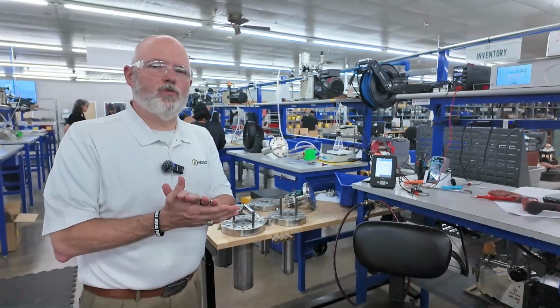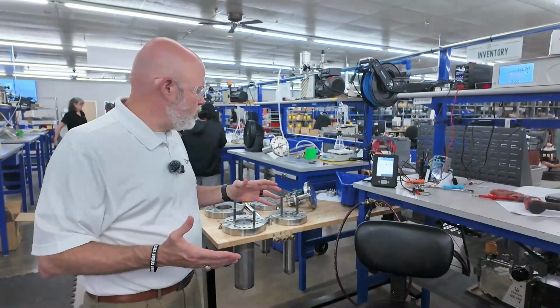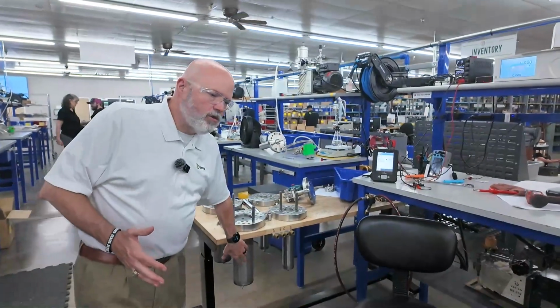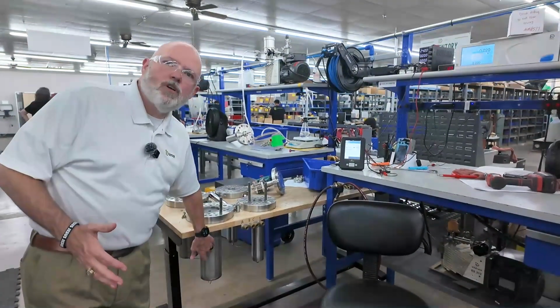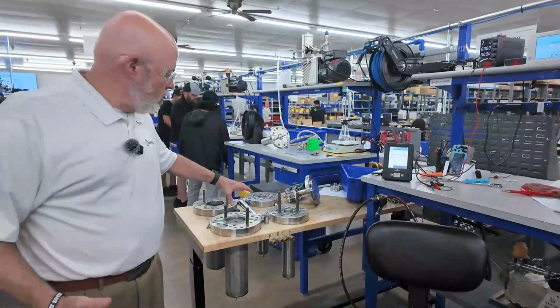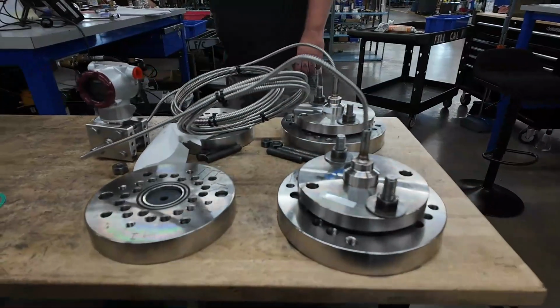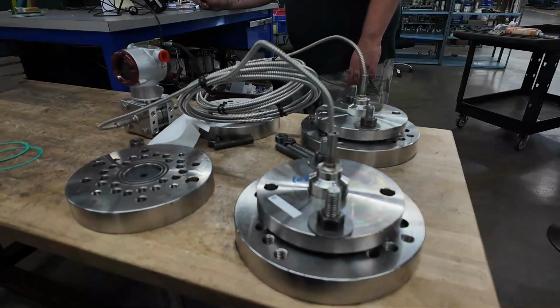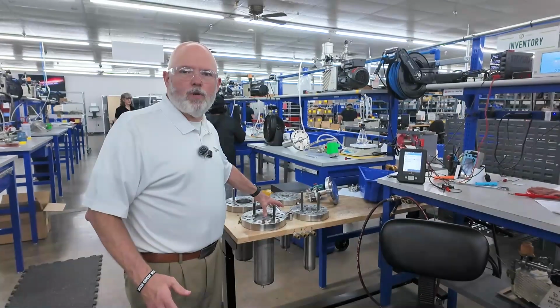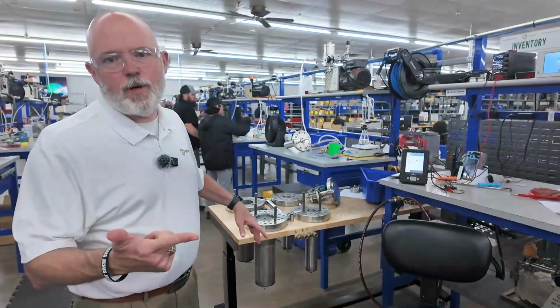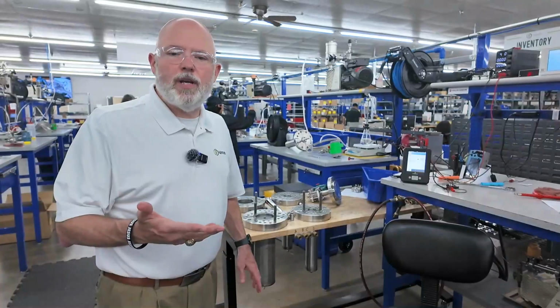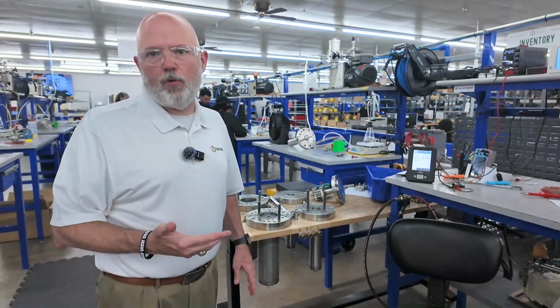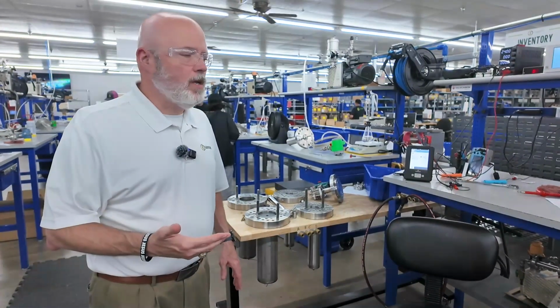So what we will do is calibrate these units. We simulate the process pressure right here through these fixtures. We mount the diaphragm seals up and simulate the pressure, testing minimum, maximum, and 3 points in between to show linearity of the system.